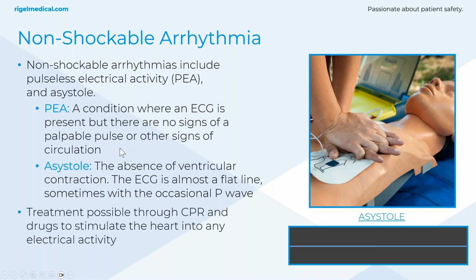And when this occurs, if you're using an AED like this one, and it sees either of these arrhythmias, it should let you know that there's no shock advised. If it's not, then there's something wrong with the AED. But they are very reliable when it comes to assessing the types of arrhythmias when they're being measured. So again, it just highlights the importance of some of these self-tests and also performance testing.